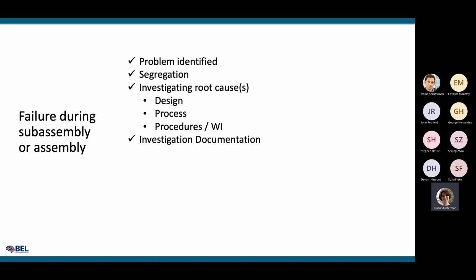We have an approved raw materials and we started with production in accordance with the procedures and instruction we determined and approved. And problem identified during this stage. Once again, we need to segregate the sub-assembly or finished device or assembly, we use the same techniques as with raw materials, red labels and designated areas. We should analyze the process, procedures, work instructions, equipment to identify the cause of non-conformancy. The results of this investigation shall be identified, corrected, and documented.